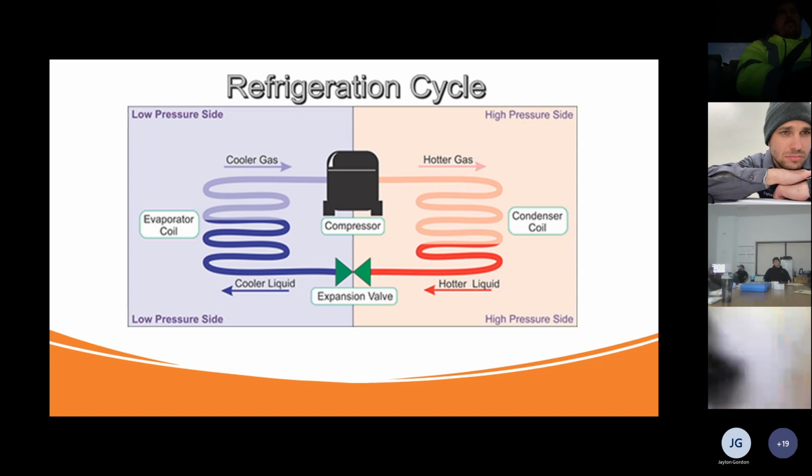Charging liquid in the suction after it's running, yes, but don't go over 20 PSI than what the suction pressure is. Correct. Yep. Hey, can I add something too, really quick, to elaborate more on that aspect?